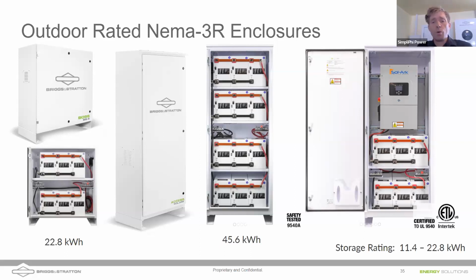I would encourage one of the battery cabinets. The reason is that battery cabinet can also be made to maintain a bit more heat. You can even put the batteries up on insulated foam, or actually incorporate heating pads into these cabinets. So if you're really worried about temperature and want to get the full use out of that battery in a cold environment, and you're going to be mounting outside, I would encourage the use of a battery cabinet like one of these.